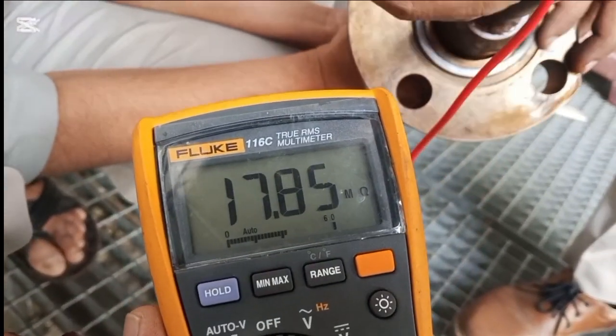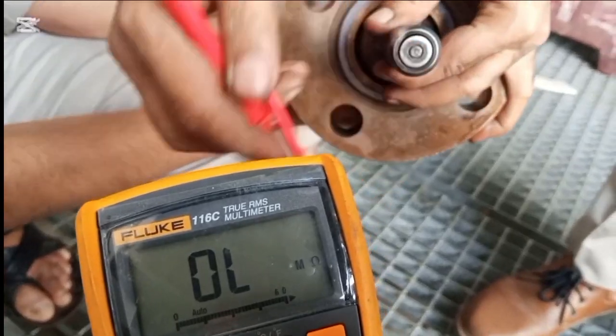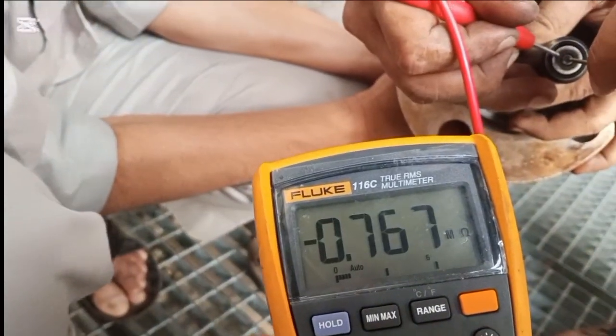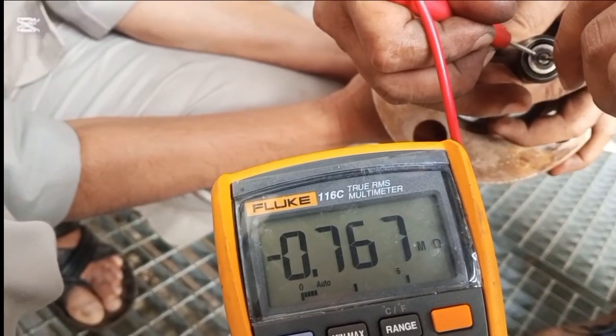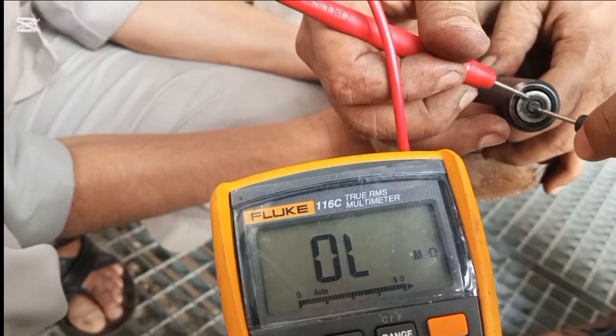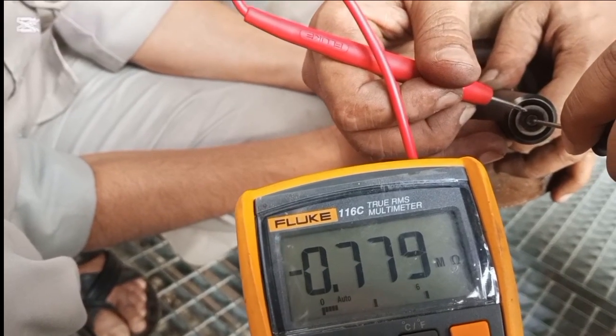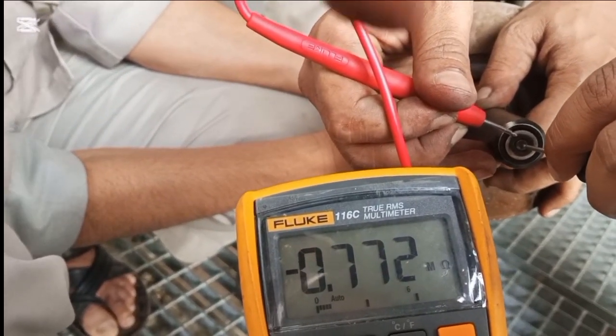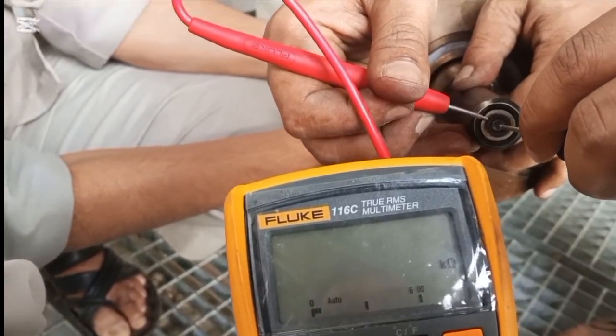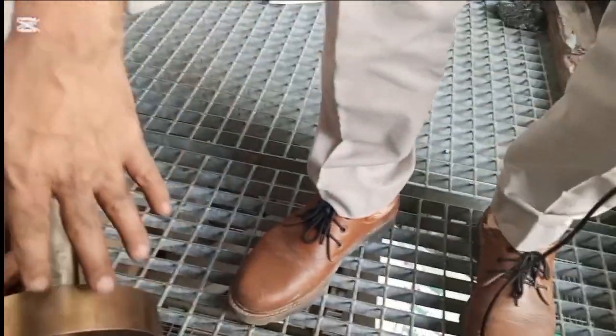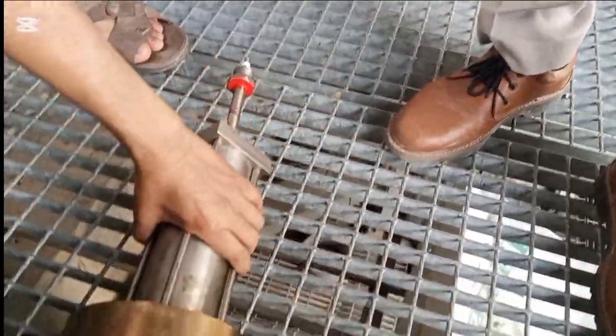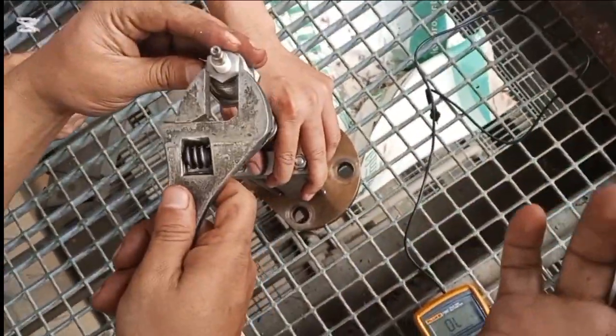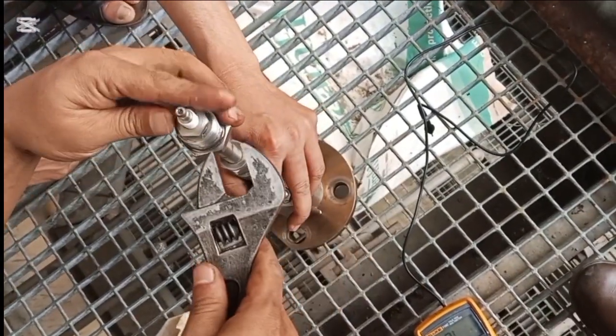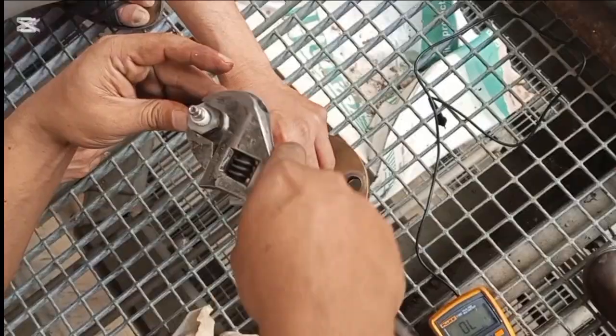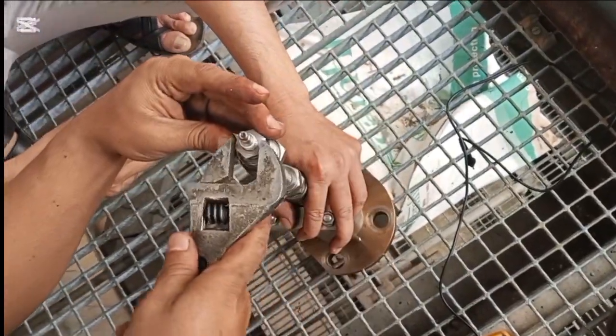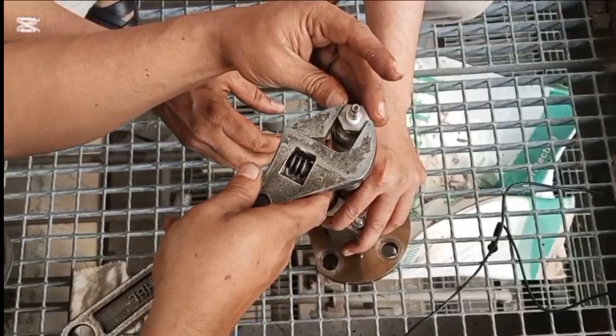If we measure this by a megger, then we will get the accurate value. Here its resistance we are measuring by multimeter, but it shows a different value each time. But after that, when we measured the continuity, we found a higher value, and the resistance value was not constant. So we tried to open the electrode from its complete base.